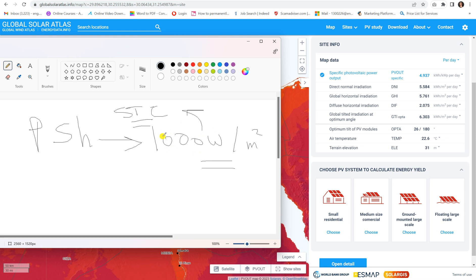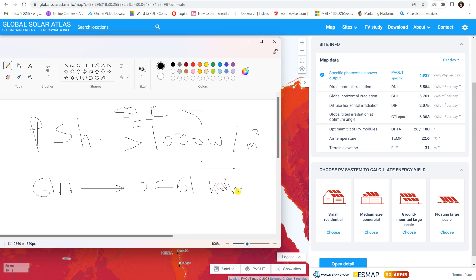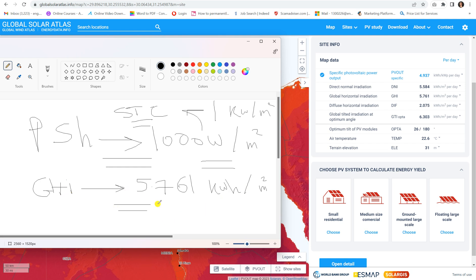The STC conditions are: 1000 W/m², 25°C, and air mass 1.5. The GHI value here is 5.761 kWh/m². Since 1000 W/m² equals 1 kW/m², the GHI value of 5.761 kWh/m² means: GHI equals peak sun hours multiplied by 1 kW/m².